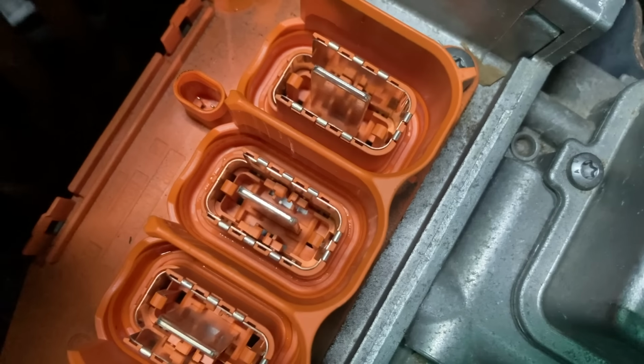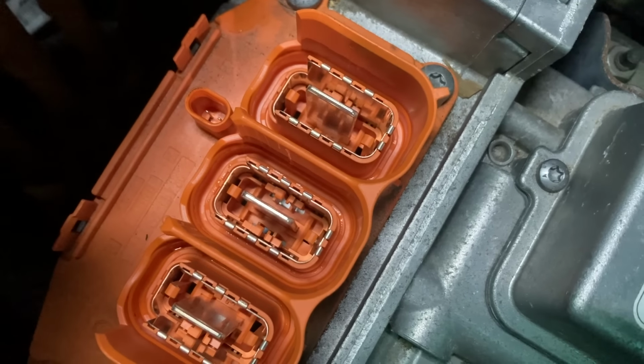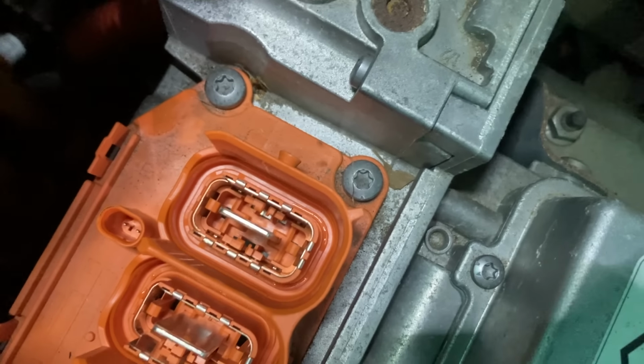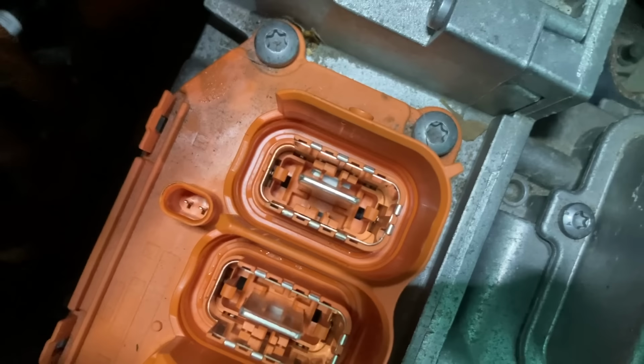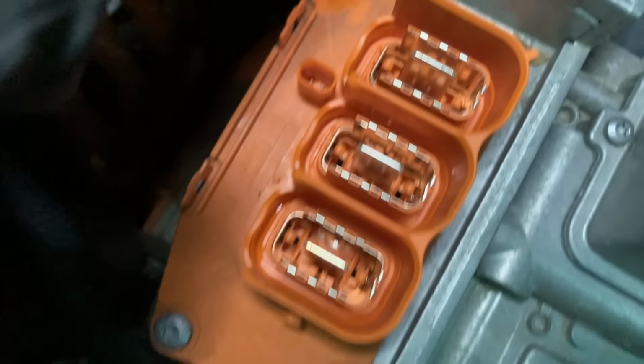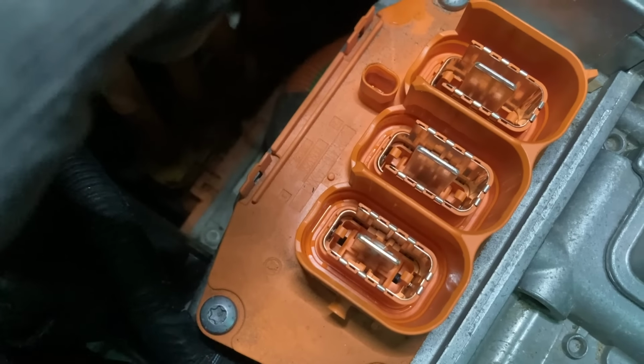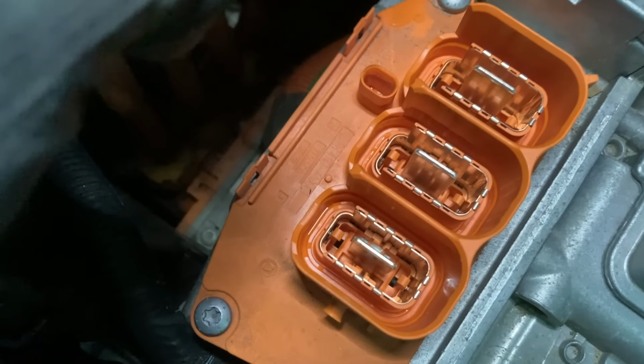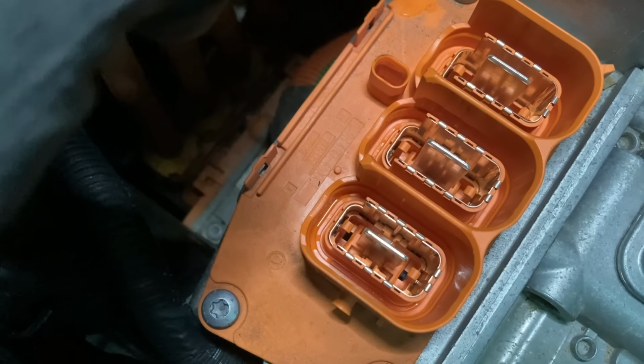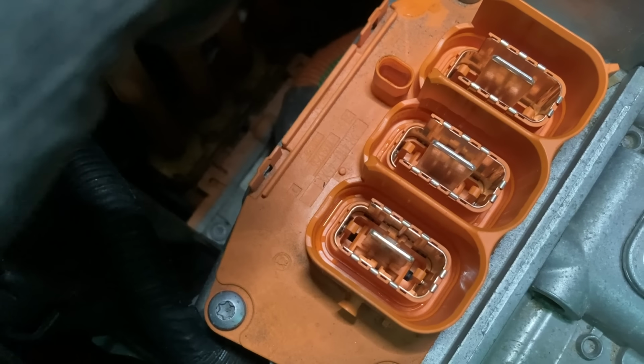Same there, can't see any. I'm looking with my eye, hopefully you can see it clearly. Sometimes when I go too close with the camera it can't focus, but no, it doesn't look like there's any, just a bit sort of on the seal, or probably around the seal, and as I've removed it, it's just moved down slightly further. So we can mop that up and double check what it is, but okay, a little bit concerning, but we shall carry on.